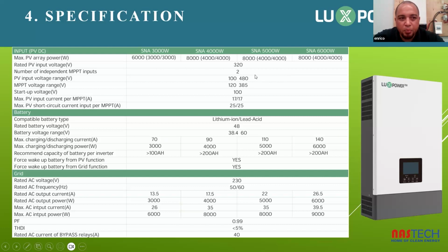The rated PV input voltage is 320. There's a dual MPPT. It's a wide photovoltaic input range from 100 to 480 volts. This is, of course, the DC voltage that's coming from the panels. This is the MPPT range. It's a slightly narrower range. The startup voltage for the PV, the solar panels, is 100 volts.